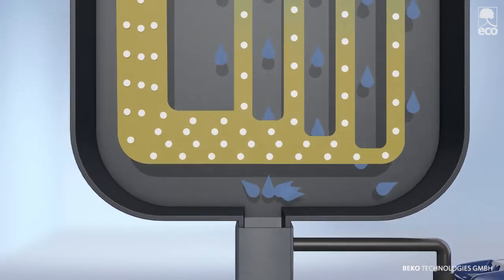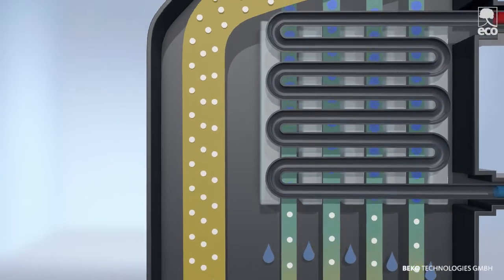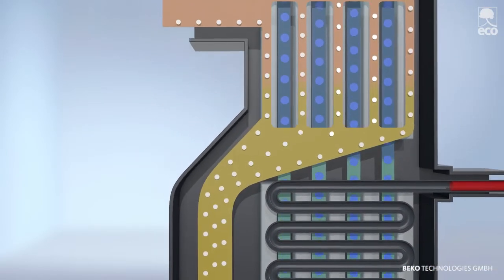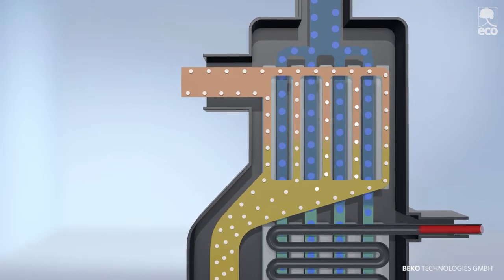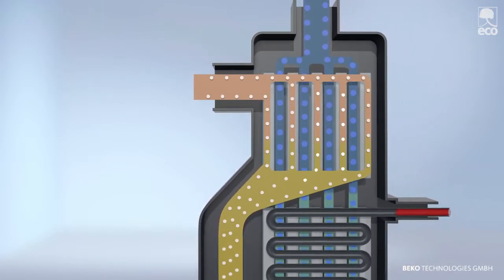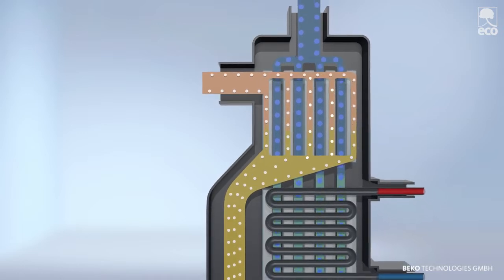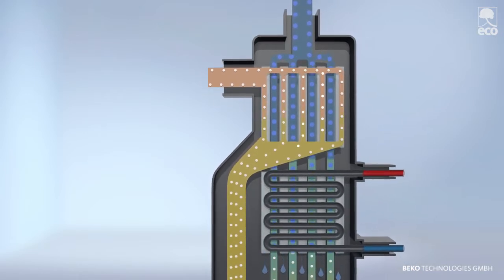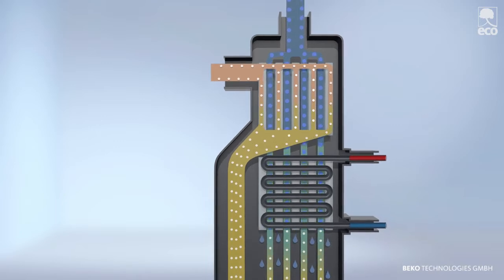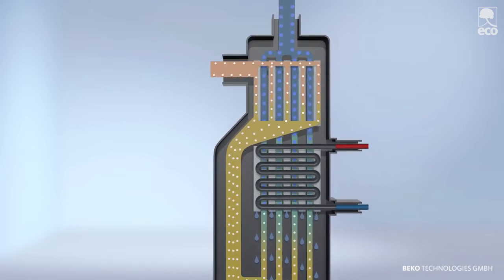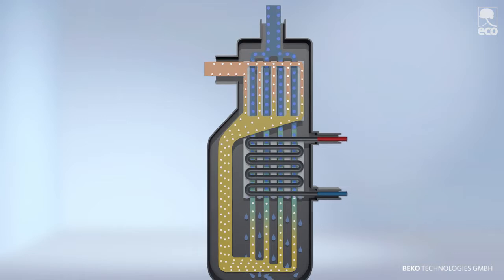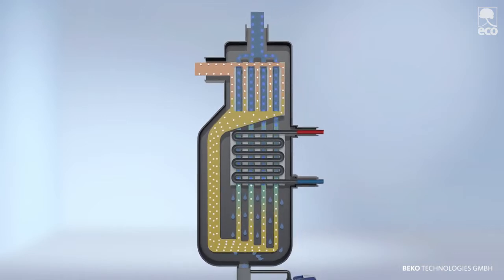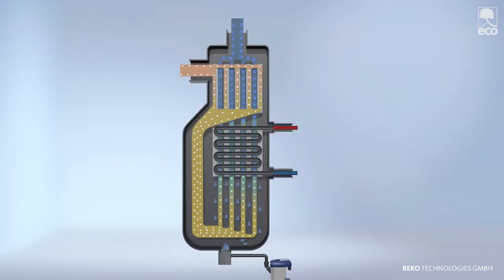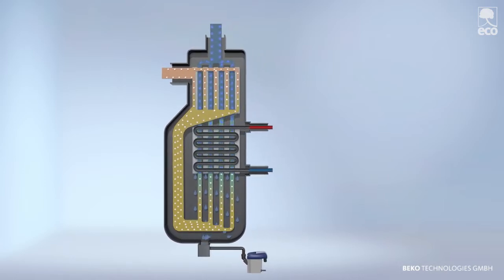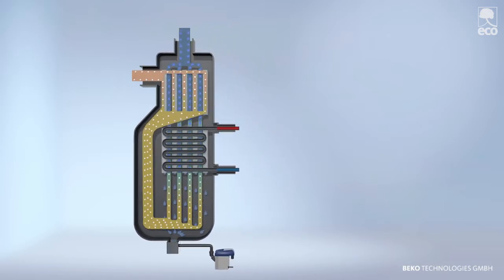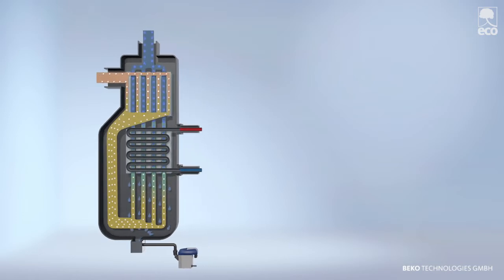The cool, dry compressed air next flows through the upper section, again past the entering air, cooling it as before in a countercurrent process, and is thereby reheated. This further reduces the relative humidity, making the air even drier. The countercurrent principle used within the air-to-air heat exchanger already increases the drying effect and the energy efficiency of the Drypoint RA Eco. Thanks to the streamlined construction, the compressed air passes almost resistance-free through the vertical heat exchanger without noticeable deflection. This minimizes pressure loss, thus lowering the system's energy consumption.